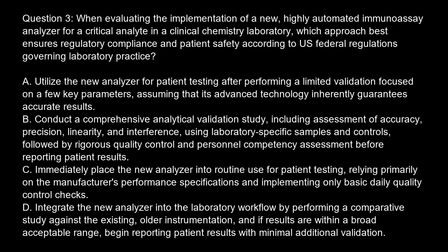Option A. Utilize the new analyzer for patient testing after performing a limited validation focused on a few key parameters, assuming that its advanced technology inherently guarantees accurate results. Option B. Conduct a comprehensive analytical validation study, including assessment of accuracy, precision, linearity, and interference, using laboratory-specific samples and controls, followed by rigorous quality control and personnel competency assessment before reporting patient results.